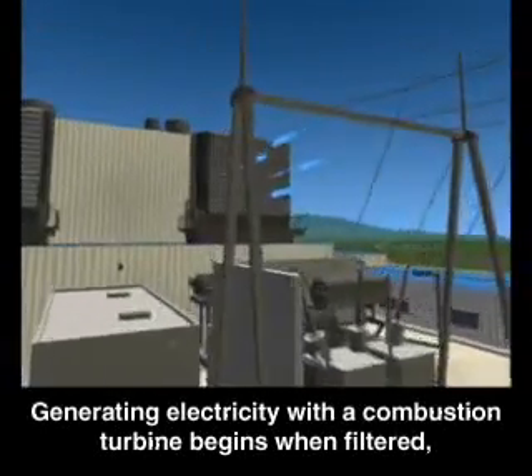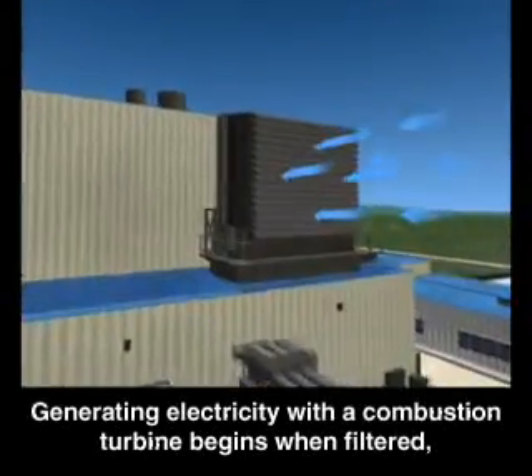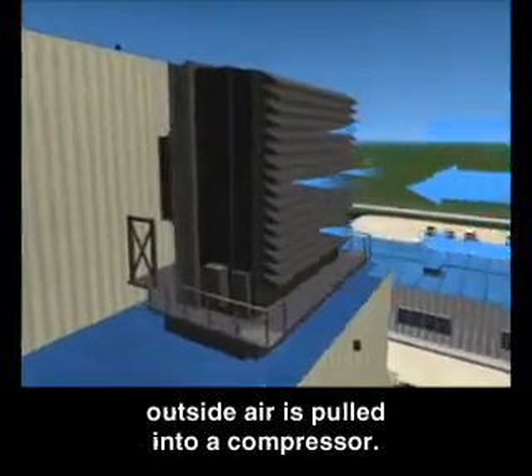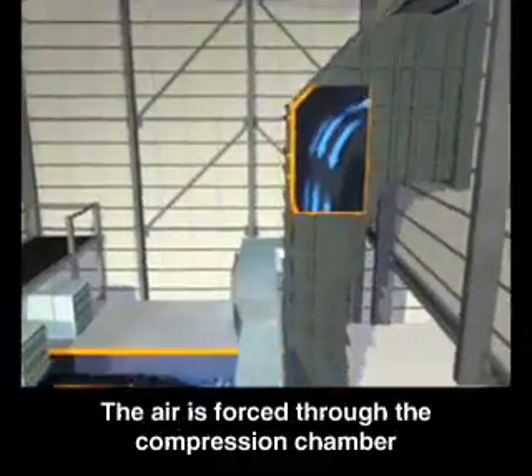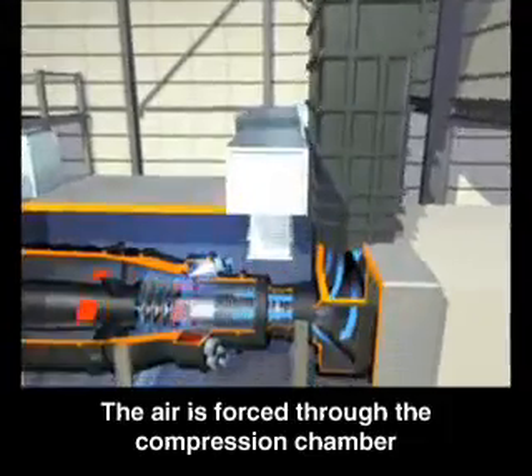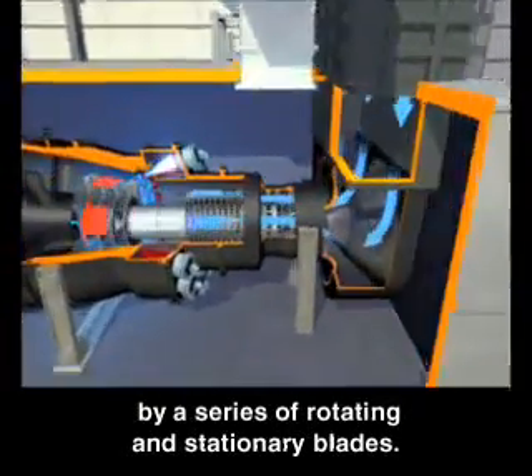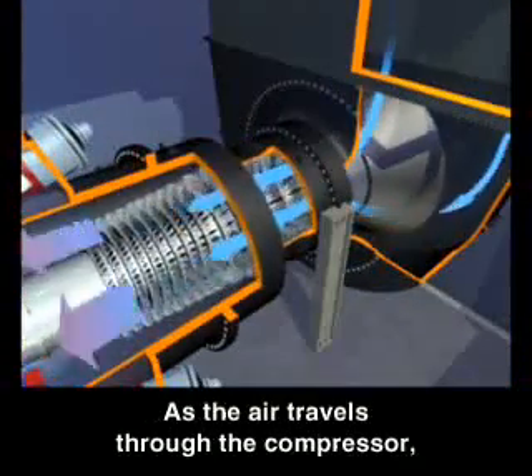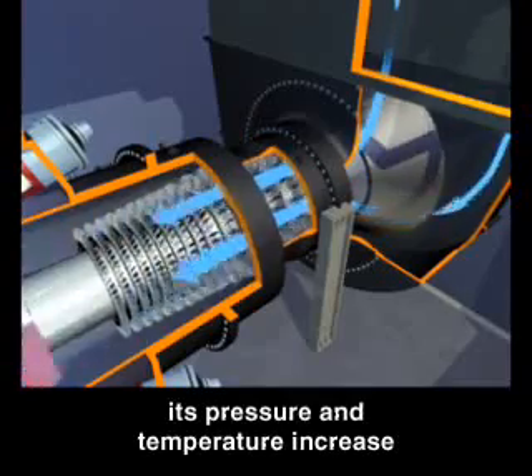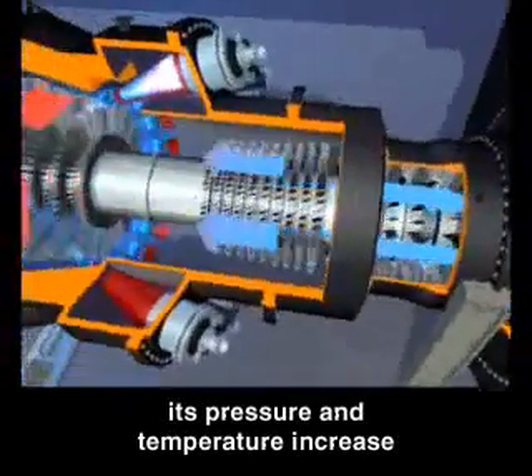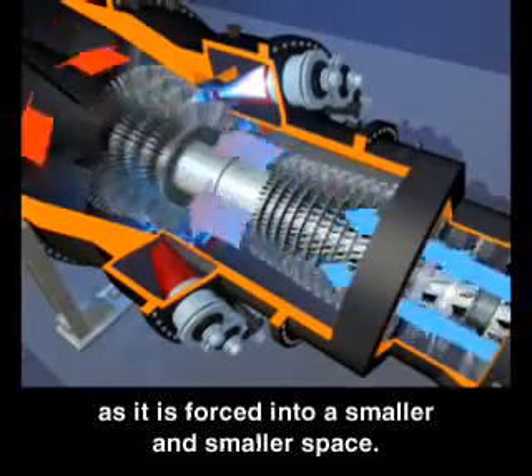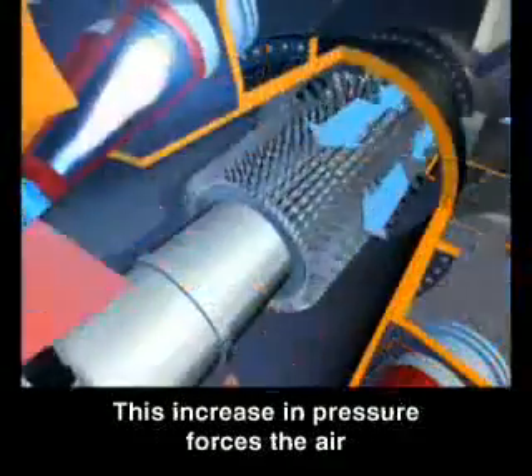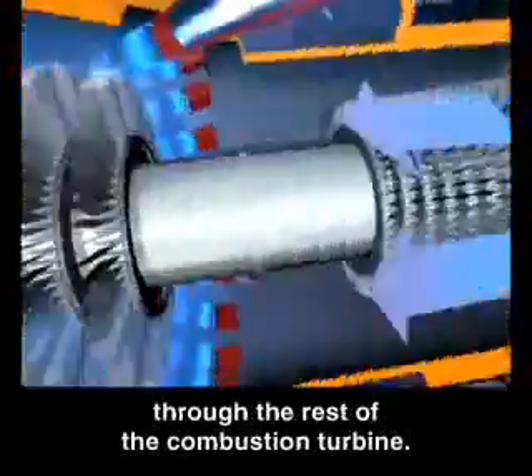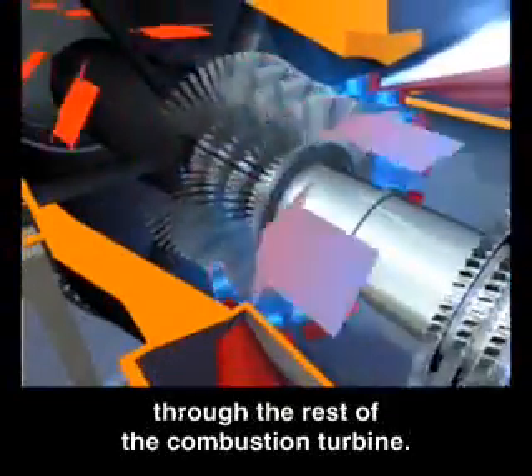Generating electricity with a combustion turbine begins when filtered outside air is pulled into a compressor. The air is forced through the compression chamber by a series of rotating and stationary blades. As the air travels through the compressor, its pressure and temperature increase as it's forced into a smaller and smaller space. This increase in pressure forces the air through the rest of the combustion turbine.